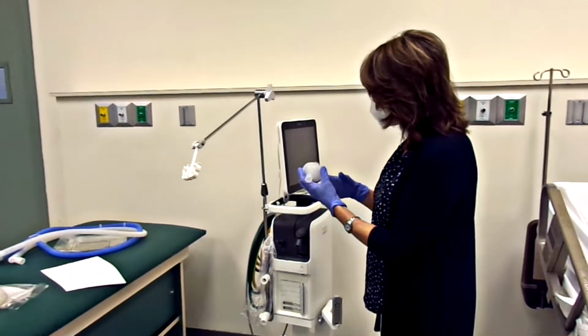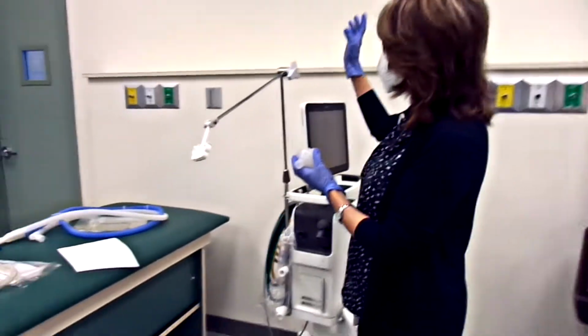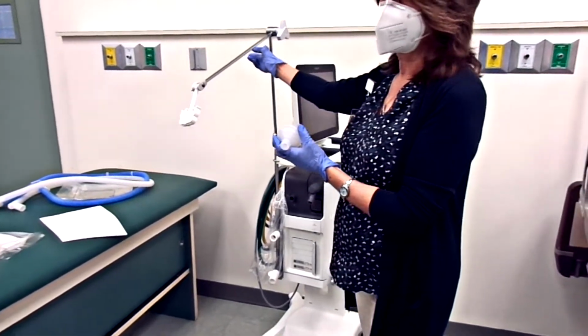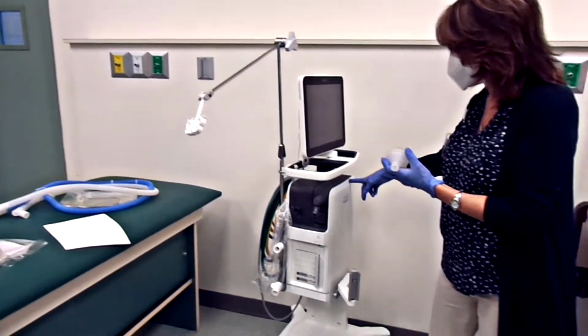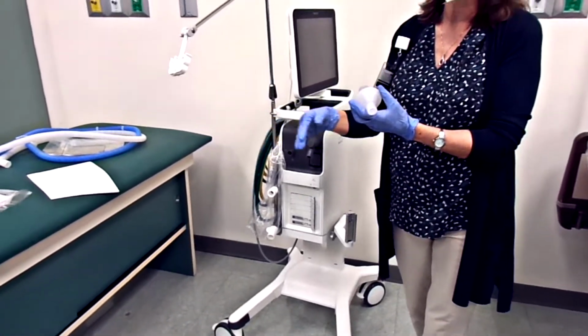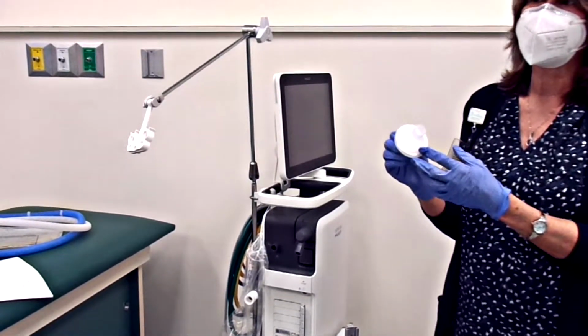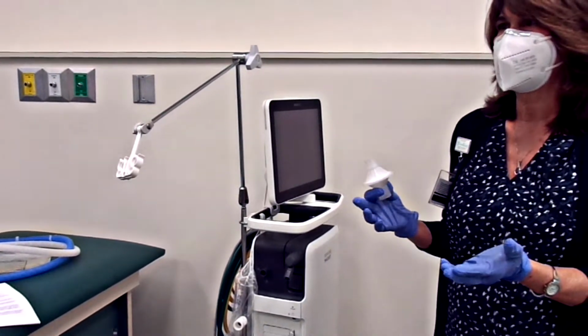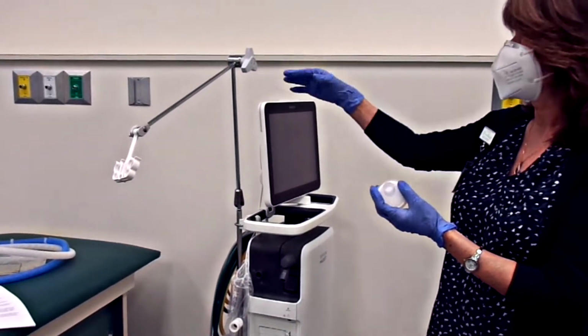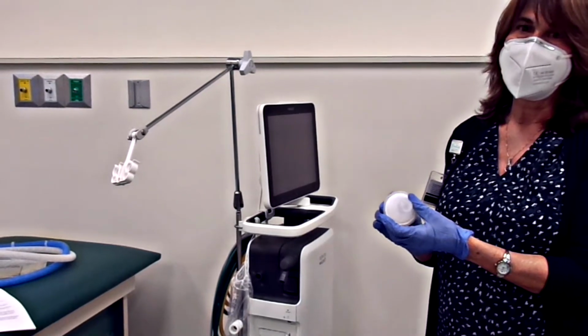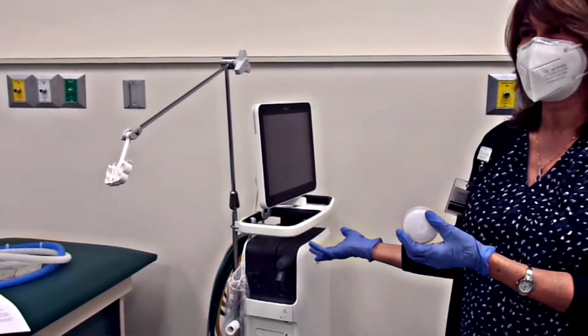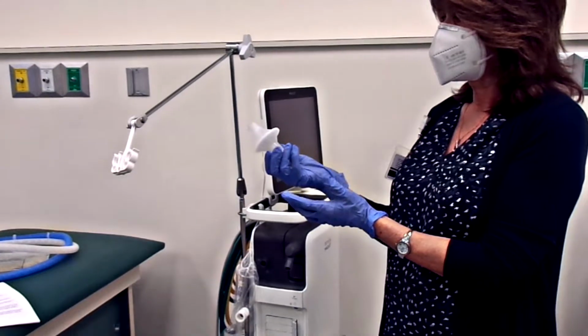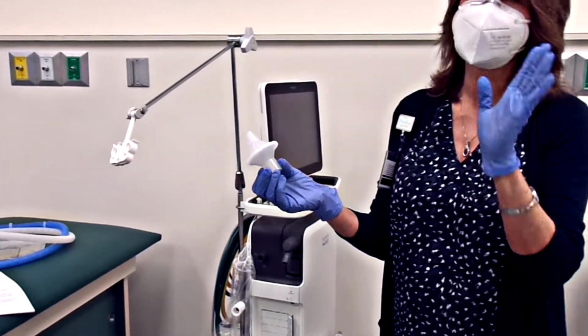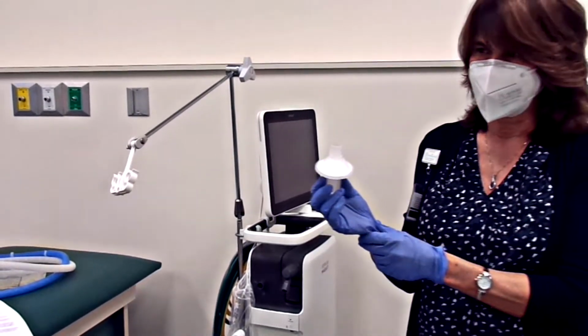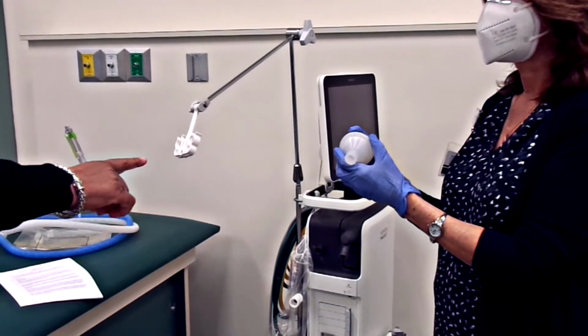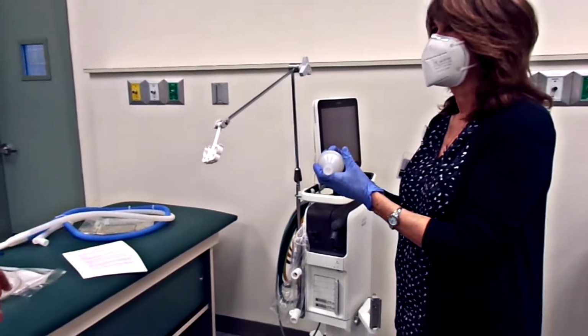So when we put it on the inspiratory side, it's air that comes from the gas outlets, travels through the ventilator, and then goes into the patient's circuit. So it's not going to have any contamination in it, because that's just cold, dry air that's coming through. And the internal components in the ventilator don't get contaminated. So this is a lower level filter, but it's perfect for the inspiratory side. So air through, filter out.